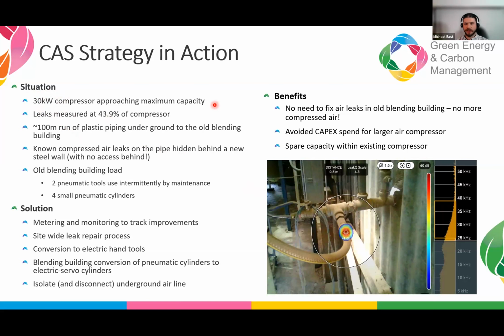The site thought, well, we've got to do something with energy. A leak survey is always a good idea, so they did that and discovered that 44% of the compressor output was being consumed by leaks. You might look at that and think, great, there's the answer, just fix the leaks and you've got capacity back in your compressor.